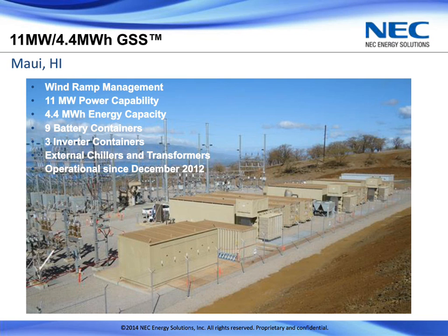Beyond the basic battery system, we also coordinated other assets on this site. There was a voltage regulation requirement I mentioned earlier. To regulate voltage at the point of interconnection, there are switched static capacitor banks in the substation yard, and the wind turbines have a certain amount of reactive power capability. Our system was responsible for dispatching that capability to meet those voltage regulating requirements.